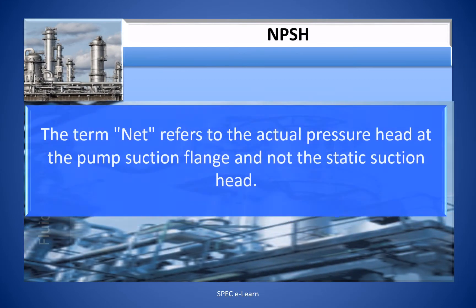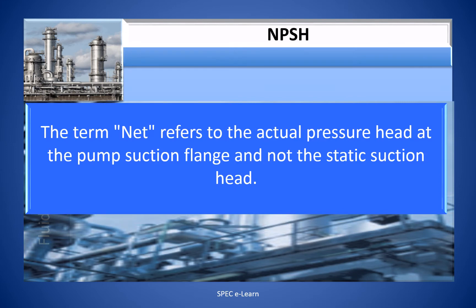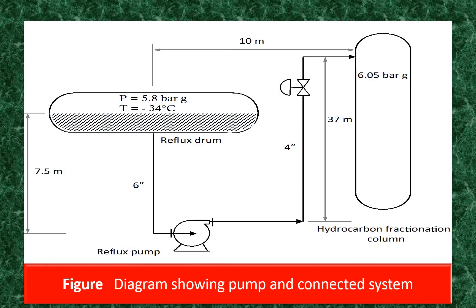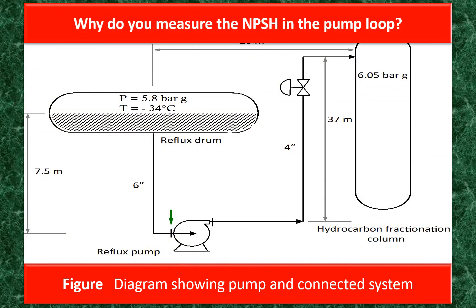The term 'net' refers to the actual pressure head at the pump suction flange and not the static suction head. NPSH required is denoted as NPSH required, and is a function of the pump design. NPSH is measured at the pump suction flange — the point at which the velocity of the liquid is maximum as it accelerates toward the eye of the impeller.